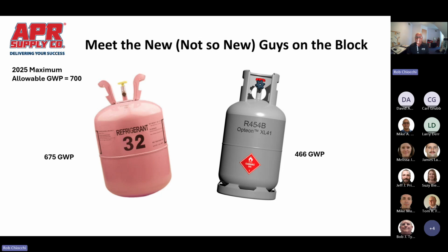They both have their pluses and their minuses. R32 is a single component refrigerant, considered easier to use because of that. But R454B has been chosen primarily in the unitary market as the refrigerant of choice because of its lower global warming potential. As part of the AIM Act that was enacted in 2020, the EPA stipulates that no manufacturer can produce a piece of unitary equipment that uses a refrigerant of a global warming potential above 700.